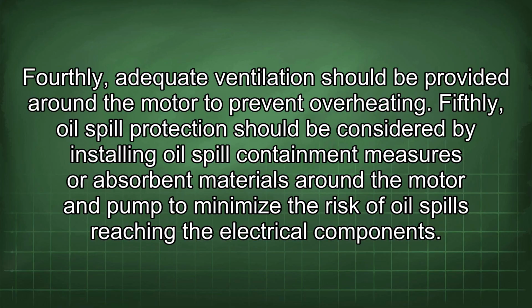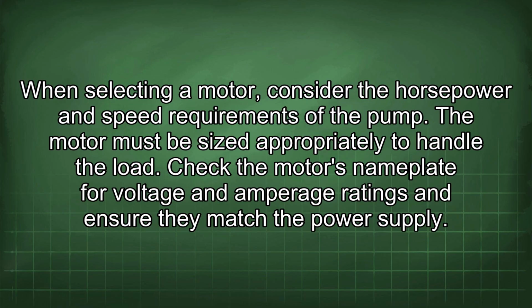Fifthly, oil spill protection should be considered by installing oil spill containment measures or absorbent materials around the motor and pump to minimize the risk of oil spills reaching the electrical components. When selecting a motor, consider the horsepower and speed requirements of the pump. The motor must be sized appropriately to handle the load. Check the motor's nameplate for voltage and amperage ratings and ensure they match the power supply.